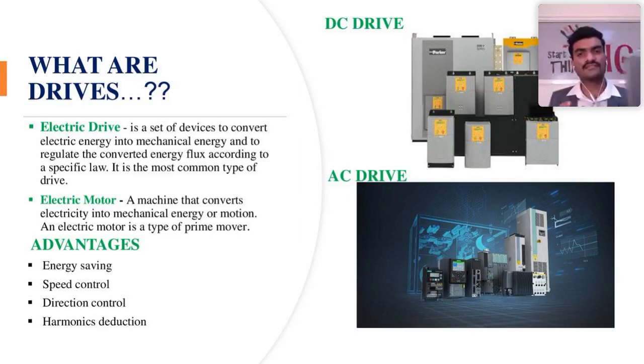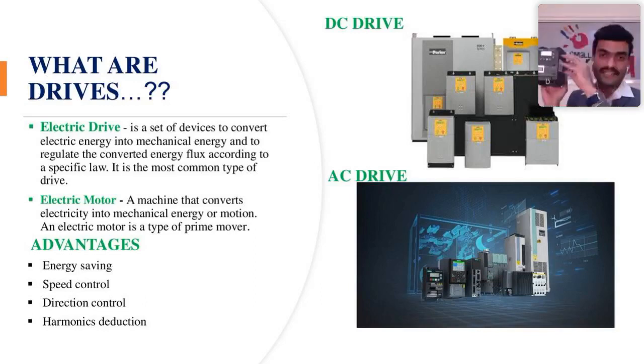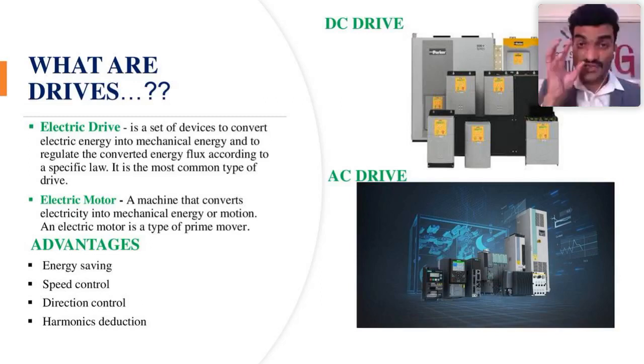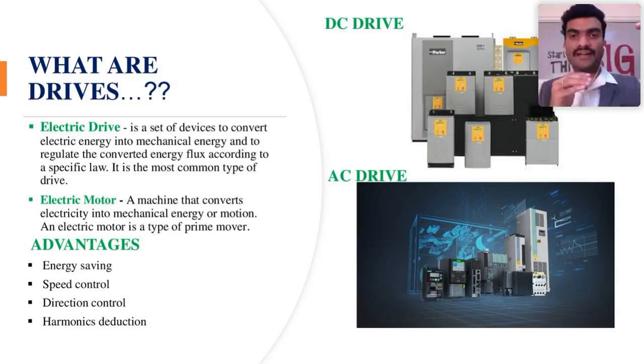Okay, how does this VFD perform? What is the principle? It takes AC input and converts it into DC. It stores the DC inside the capacitor bank, and then converts that DC to AC again at the inverter, and that converted AC is given to your motor. So this is how the drive functions: AC to DC conversion, then from DC to the required AC, which is sent to the motor. So it is also a safety device for the motor. If some overcurrent comes, it will stop at the drive only, not at the motor. So it offers energy savings. You can control speed and direction, and harmonics are also reduced here.